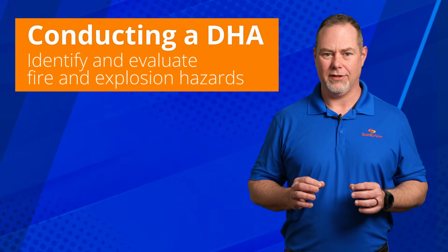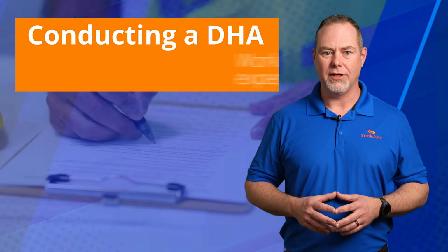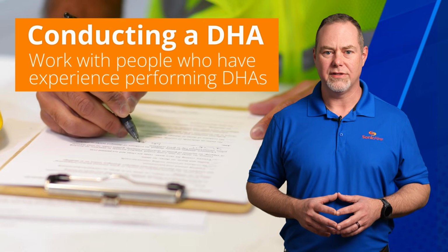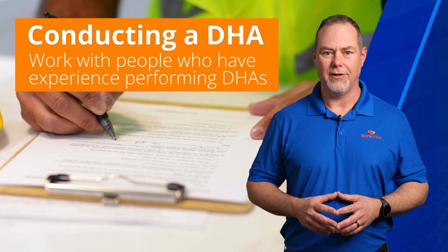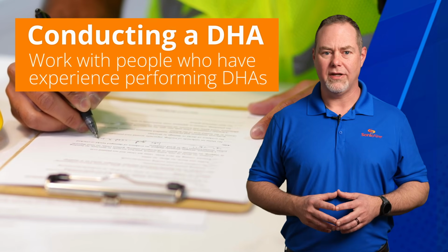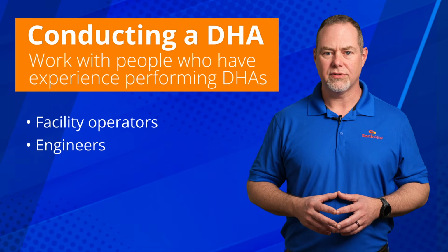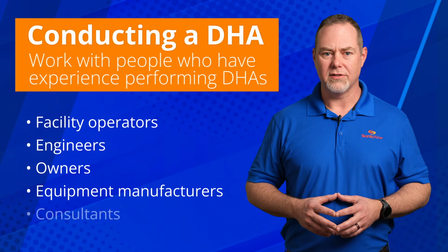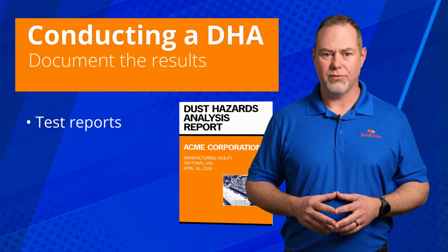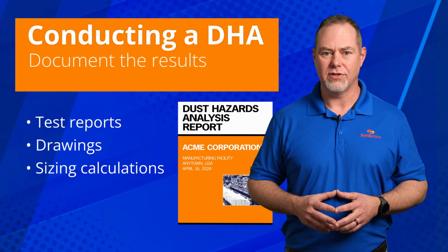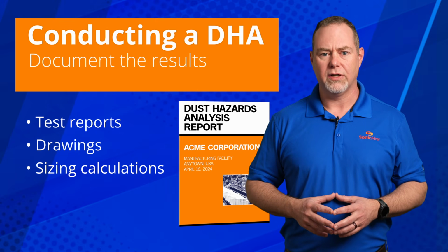This may sound a little daunting, which is why NFPA 660 says that in order to conduct a DHA, you'll need to work with a qualified person who possesses documented experience and education regarding methods for performing a DHA. You'll probably even want to assemble a small team. The individuals involved in the DHA could include facility operators, engineers, owners, equipment manufacturers, or consultants. And when you're all done, the resulting DHA document should include test reports, drawings, and sizing calculations for all areas of the process or facility determined to be a combustible dust hazard.